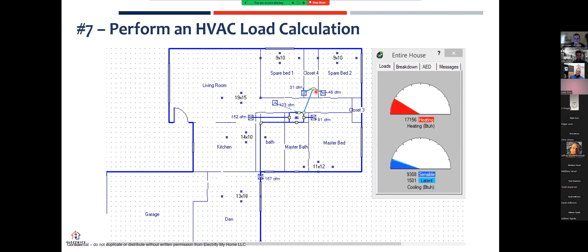This is the value of doing the proper load calculation. We have two rooms that are both 9 foot by 10 foot, spare bedroom 1, spare bedroom 2. And one of them needs considerably more airflow. The way we explain this to our customers is, cubic feet per minute of air is one thing we can say. But then I always ask, do you know how much a cubic foot of air is? It's about the size of a basketball. So in this room, I need 48 basketballs of air every minute. In this room, I need 31 basketballs of air every minute.